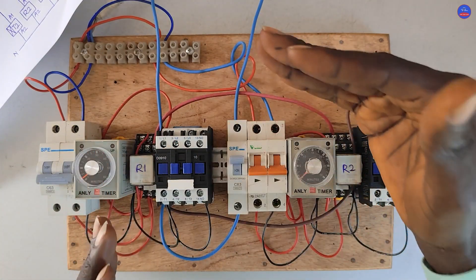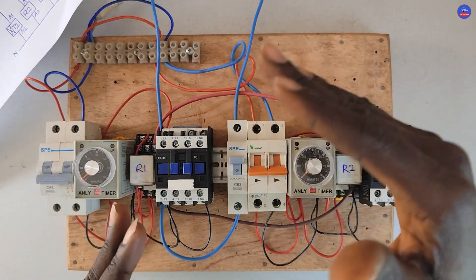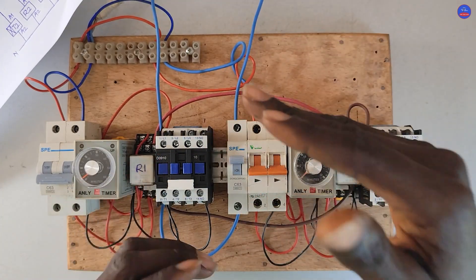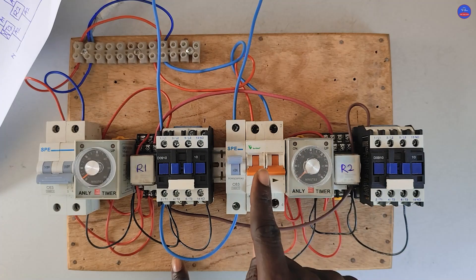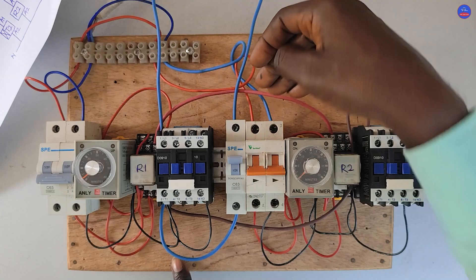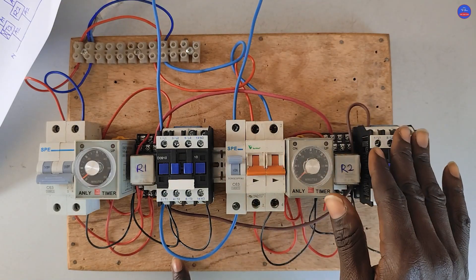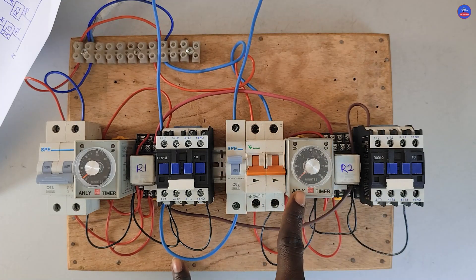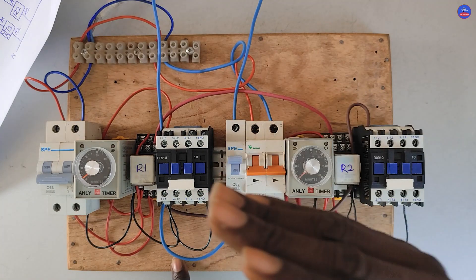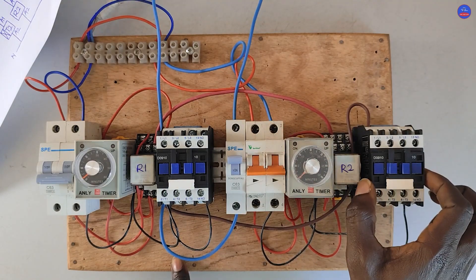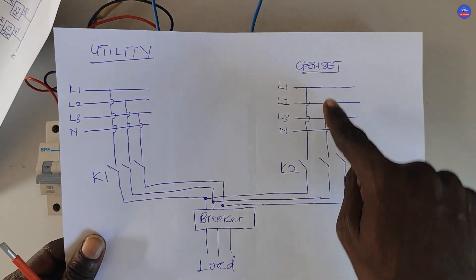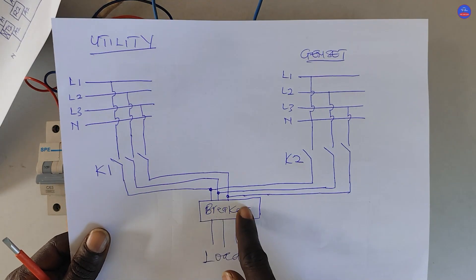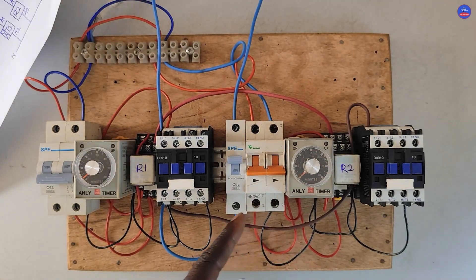When the genset starts and the voltage is okay — we get enough 230V or enough single-phase voltage — power will be applied to the control circuit. The moment we turn on the breaker, it is assumed that the generator power is available at the control side. Therefore this timer would energize and start to count. After the preset time, this contactor would energize and this contact would close, therefore the generator power will be applied to the load.